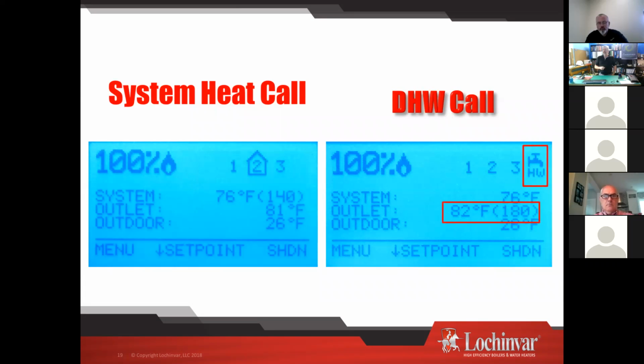And then the other thing that I have here is that 180, the outlet temperature, is now in parentheses. So in this scenario, that domestic hot water is piped directly to the boiler. So the boiler has turned off the system, the boiler pump. So it's no longer injecting to the system loop, and it's headed right out to your domestic hot water tank. Because it's doing that, it's no longer targeting the water up on the system. It's targeting it coming right out of the boiler, because that's the only spot it's going. And that's why that change is there. So the boiler knows. If it were trying to target it on the system, the boiler would overdrive itself. That's why we moved to that different spot of sensing and targeting.